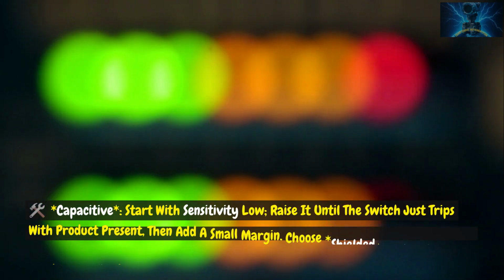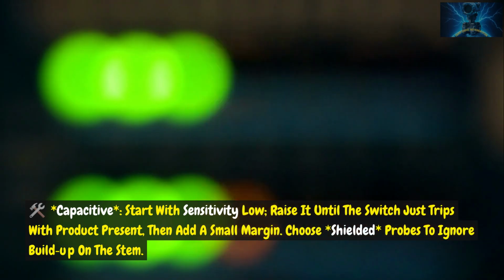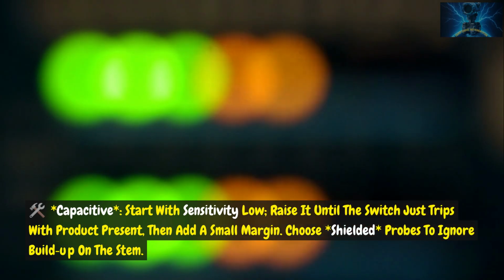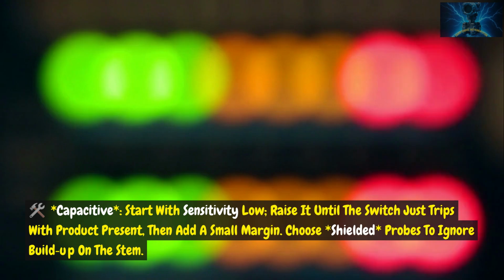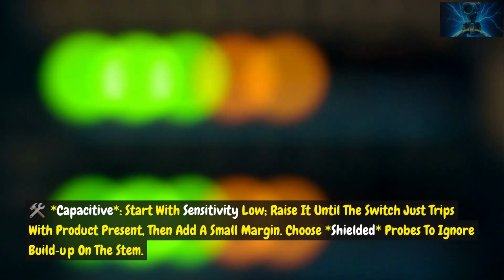Capacitive: start with sensitivity low. Raise it until the switch just trips with product present, then add a small margin. Choose shielded probes to ignore buildup on the stem.